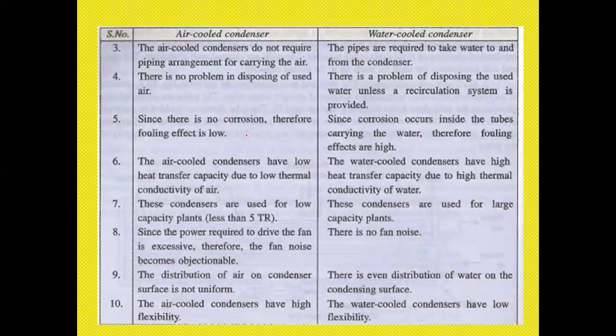Next, third point, the air cooled condensers do not require a piping arrangement for carrying air. There is also no problem of disposing of exit air. Whenever you are doing the process, the air from the chimney, the smoke, will be released out. So here also there is no problem of disposing of used air. But in the water cooled system, pipes are definitely required to carry the water to and from the condenser. There is a problem of disposing of the used water unless a recirculation system is provided.